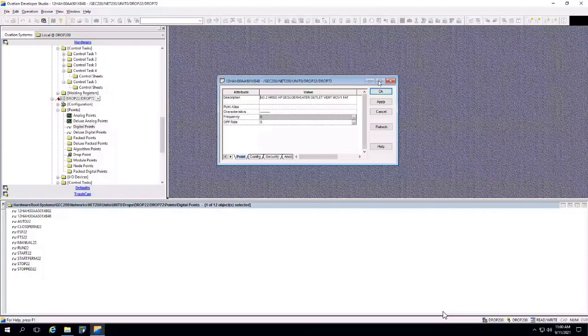Okay. Another modification for you, Amjad. You didn't define one AO point. Both these points are assigned to an analog input. I need one AI, one AO, one DI, one DO. So DI and DO you have configured correctly, but in the analog you have configured both as analog input. So delete one point and make one new AO point, analog output.